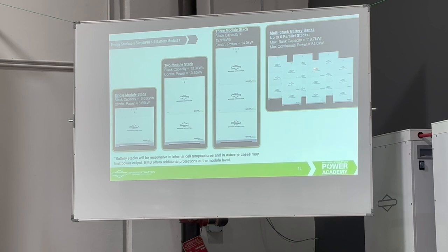You can always parallel batteries and add more to your system, up to 84 kilowatts of power out of 6 stacks, and up to 120 kilowatt hours of storage. The batteries are modular, so you could go 3, then 5, 6, you don't really have to keep consistency after the 3.